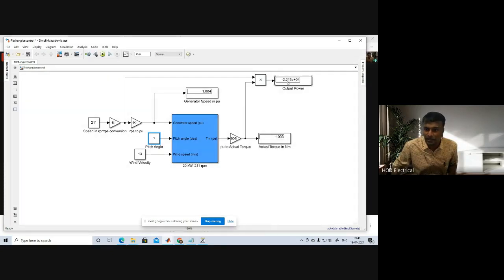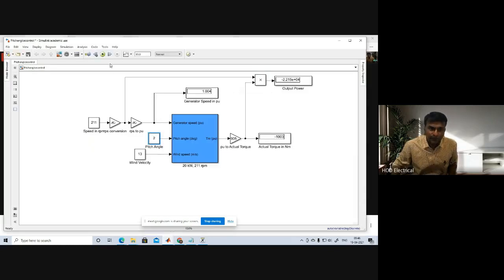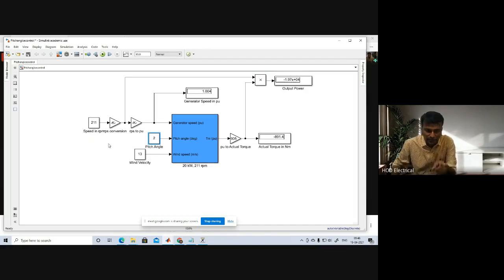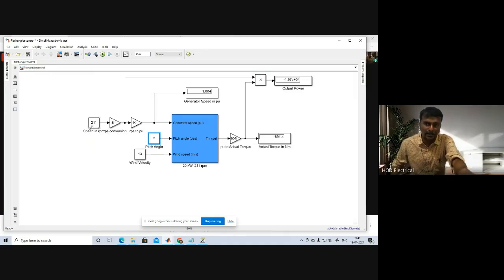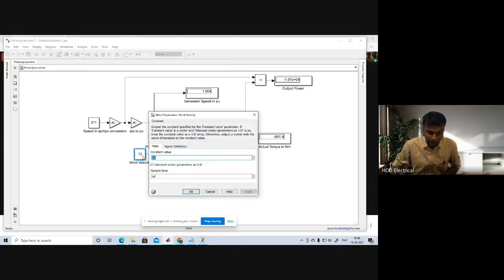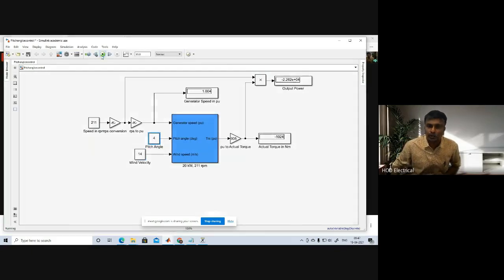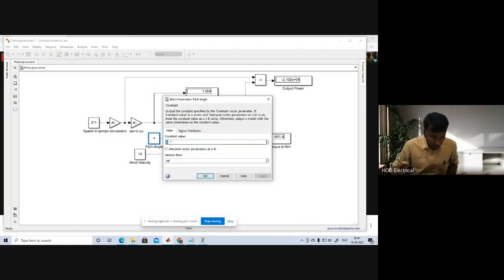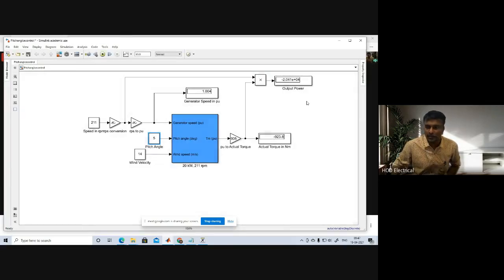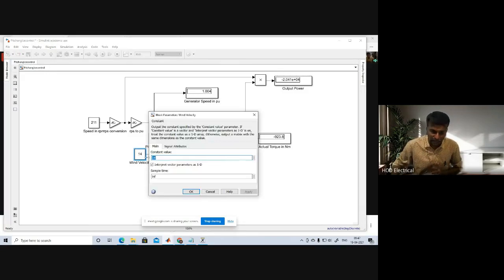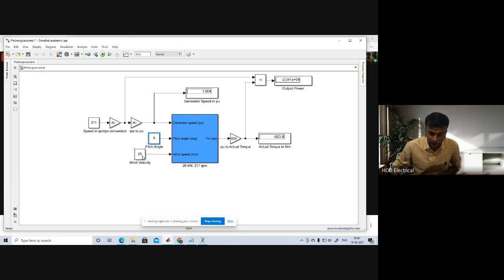If I increase the pitch angle further, we will get approximately 20 kilowatts again. Whenever wind velocity is 13 meters per second and speed is at rated speed, we cannot increase generator speed beyond that, so we increase the pitch angle to maintain rated power as constant. Then if we increase wind velocity to 14 meters per second, output power rises to 22 kilowatts, so I increase pitch angle to 4 degrees to bring it back toward 20 kilowatts. Increasing to pitch angle 5 degrees gives approximately 20 kilowatts. This way you can vary pitch angle up until wind velocity reaches 24-25 meters per second.